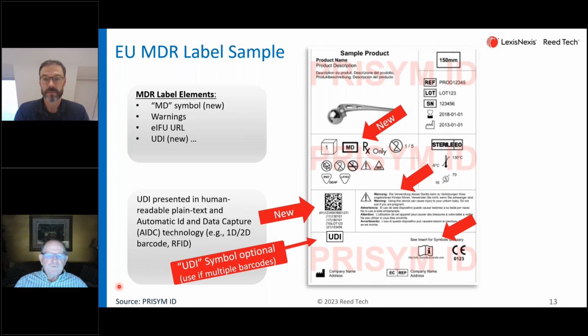But then at the other end of the spectrum, some companies that we talk to have been using their own kind of proprietary identifier, and the challenge is quite large to map the internal number that they've been using over to an acceptable standard, let's say GS1, and get the device identifiers mapped, and then lo and behold, they don't have room on their label to put this barcode. Sometimes the one-dimensional one gets pretty long, so that comes back as a challenge. Like, how do I fit this on my label?